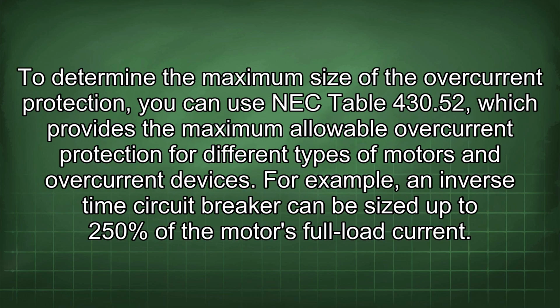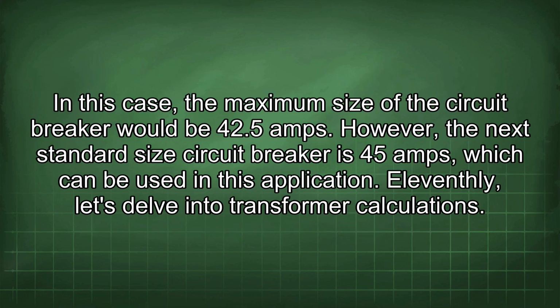To determine the maximum size of the overcurrent protection, you can use NEC table 430.52, which provides the maximum allowable overcurrent protection for different types of motors and overcurrent devices. For example, an inverse time circuit breaker can be sized up to 250% of the motor's full load current. In this case, the maximum size of the circuit breaker would be 42.5 amps. However, the next standard size circuit breaker is 45 amps, which can be used in this application. 11thly, let's delve into transformer calculations.